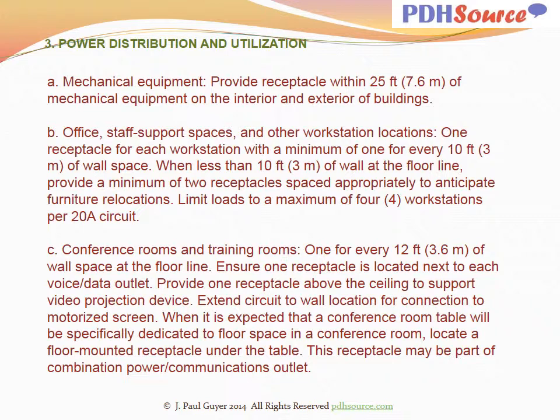Ensure one receptacle is located next to each voice data outlet. Provide one receptacle above the ceiling to support video projection device. Extend circuit to wall location for connection to motorized screen. When it is expected that a conference room table will be specifically dedicated to floor space in a conference room, locate a floor-mounted receptacle under the table. This receptacle may be part of combination power communications outlet.